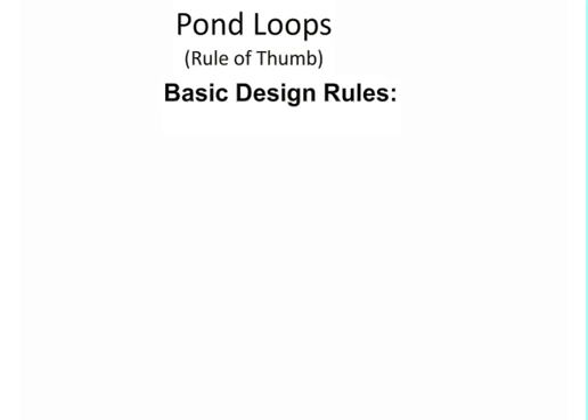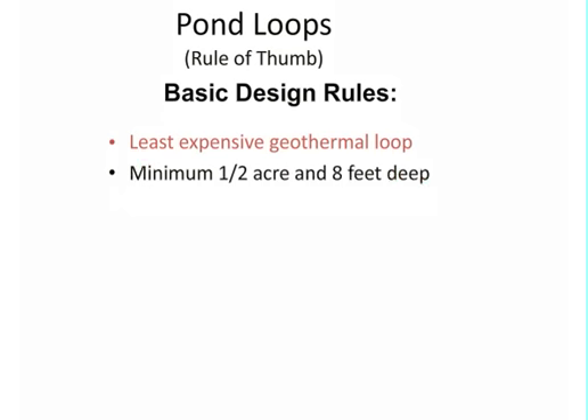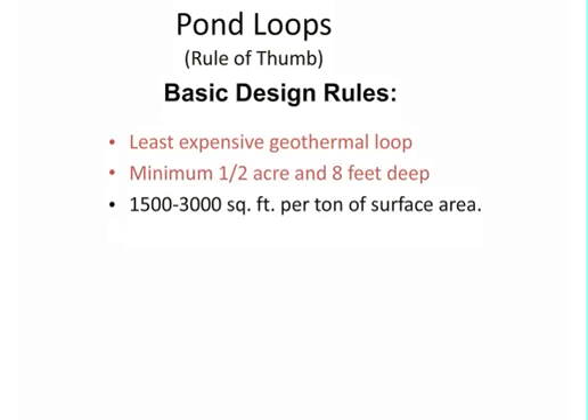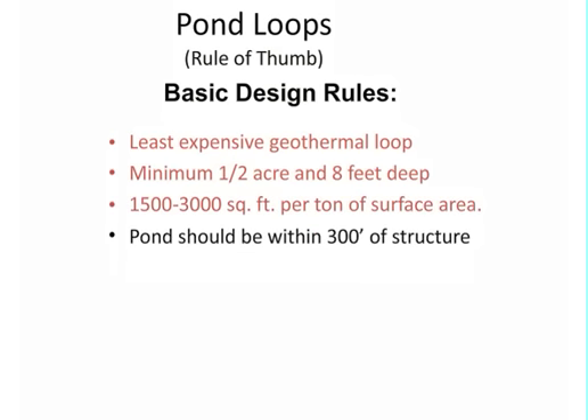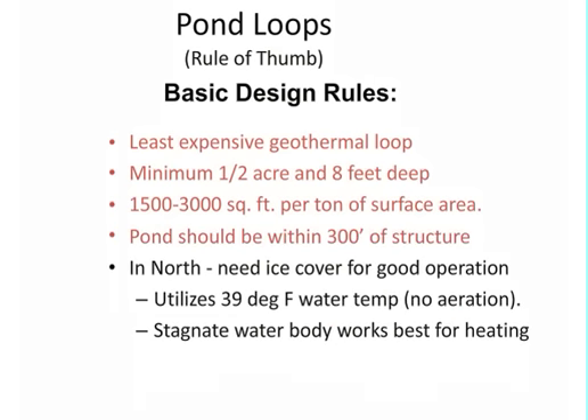Rule of thumb, and I will tell you I'm not a big fan of rules of thumb in geothermal, but it is the least expensive of your geothermal closed loops because it typically takes much less heat exchange surface area when submerged in water itself. You want to have a minimum half-acre pond, and you want to make sure you have that depth.